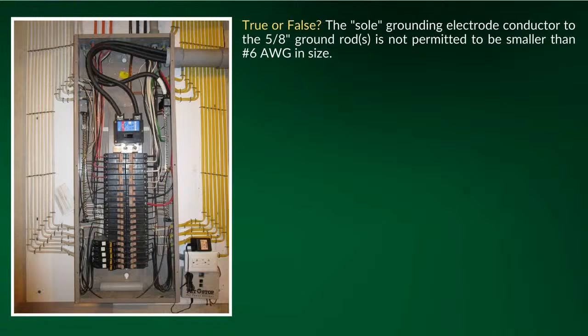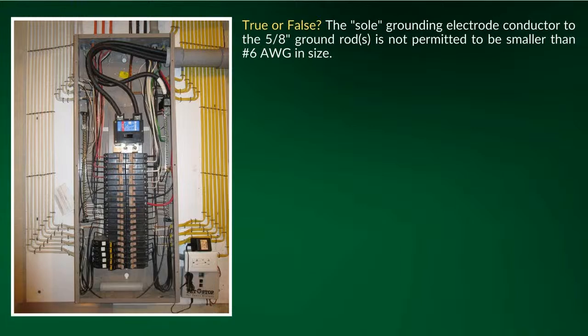And I imagine you could probably explain it a little bit better than me. That wasn't table 250-102C1. It was table 250-122 that it is now. And they did a multiplier of 0.189 when they were doing all that sizing. Now, right. One of the things I want to point out: I don't think that was 12.5%, David. Over there, when you're getting into the larger conductors, over 1,100 kcmils, at 12.5%. And that's what he's talking about.